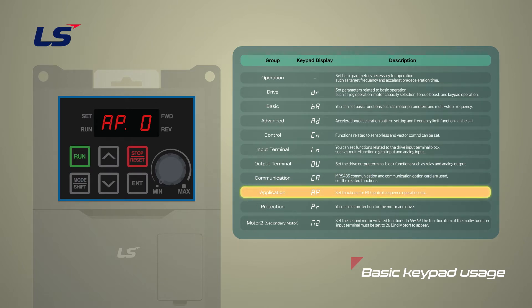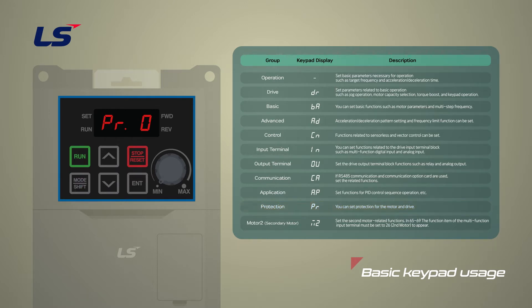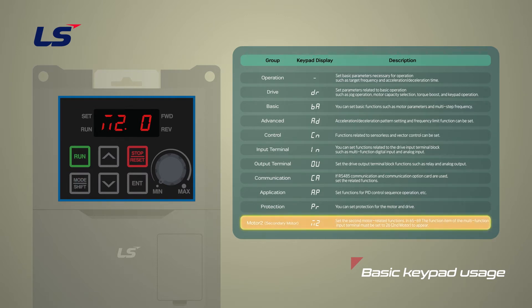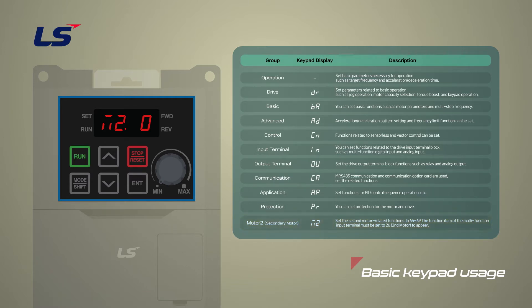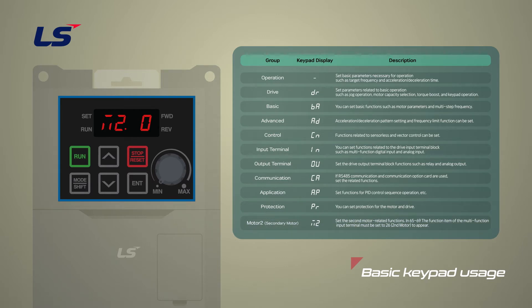The communication function group that configures communication features for RS-485 or other communication options. The application function group that configures functions related to PID control. The protection function group that configures motor and inverter protection features. And lastly, you will find the secondary motor function group. For reference, the secondary motor group appears on the keypad only when one of the multifunction input terminals has been set to 26. You can move to the first DR drive group by pressing the mode shift key once more in the last sequence group.